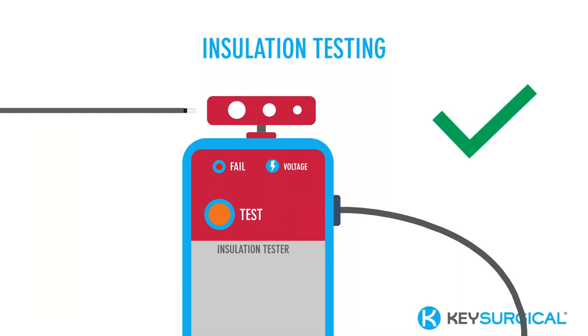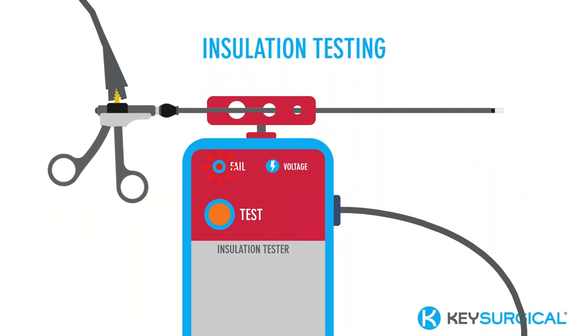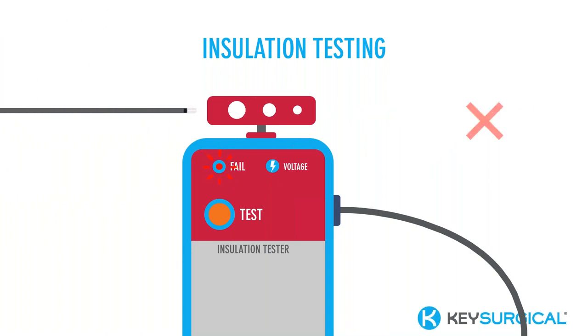So if everything is good, the machine won't do anything. If the insulation fails, you will see a fail light light up, indicating that there is an insulation failure on the shaft of the instrument. So what are the next steps in your facility policy and in the instrument manufacturer's IFU with a failure? Most of the time, it's notify your manager or instrument coordinator, and they will notify the OR for any remaining procedures scheduled for that day if it will affect that procedure.